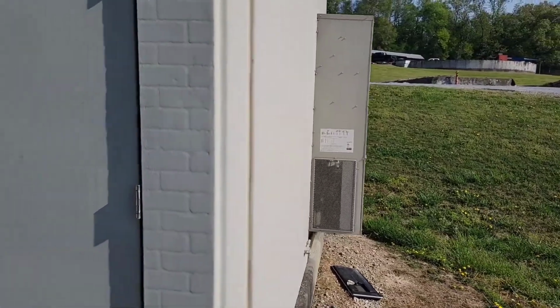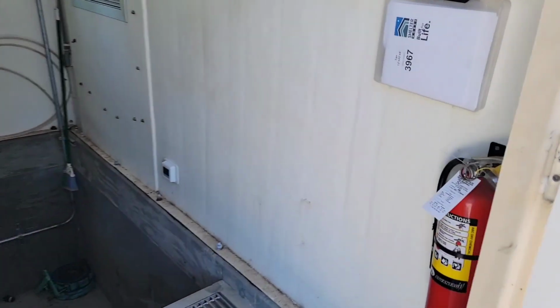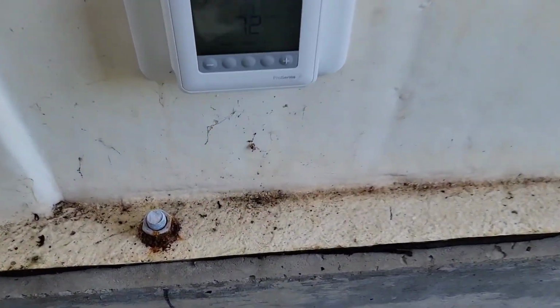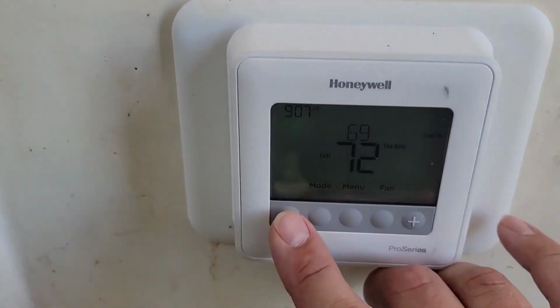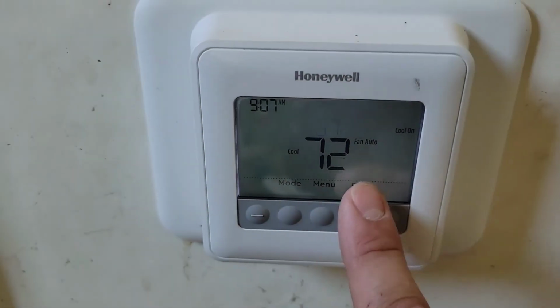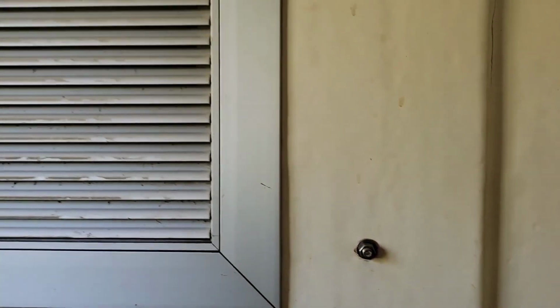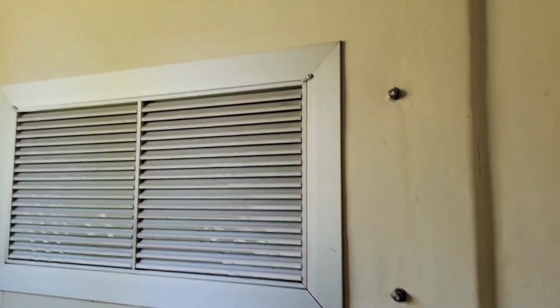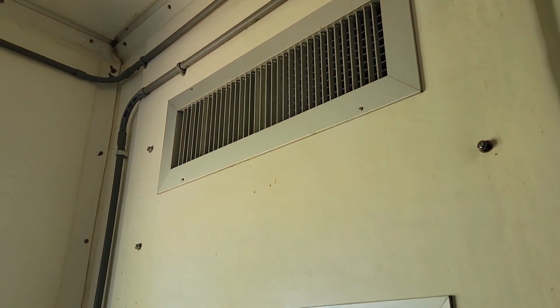Working on the old Bard unit today. Let's figure out what the thermostat's set on. Make sure it's on cooling. Thermostat set to cooling. Cool on, should be running. There's the return. There's the supply. Sounds like the fan's running. Let's go outside and check it out.